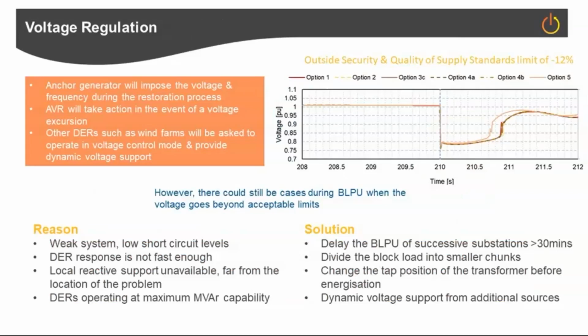Another finding is around voltage regulation. Obviously there's a big link here to the weak system of a small power island. The short circuit levels, fault levels as we call them over here in Britain, are low, and with the switching of block loads, transformers or circuits, because the system is weak and the short circuit levels are low in a small power island, you will get large voltage deviations. The anchor generator will effectively regulate the voltage within the power island, but as I said, switching the block loads, you will get this voltage dip.